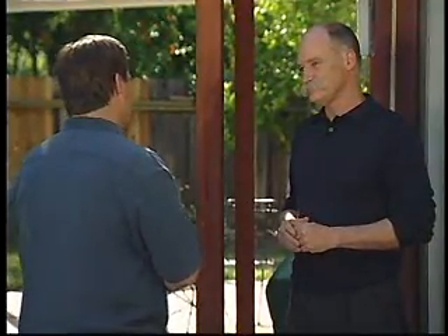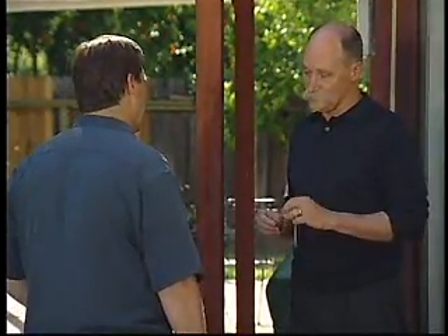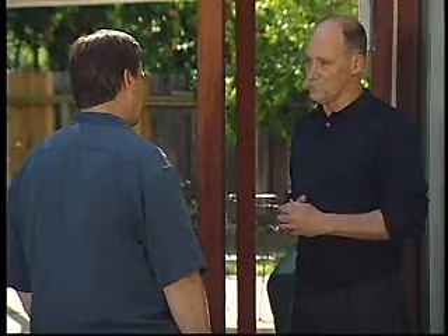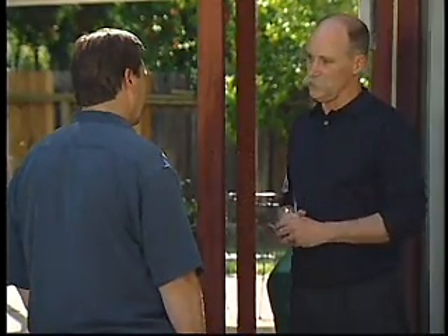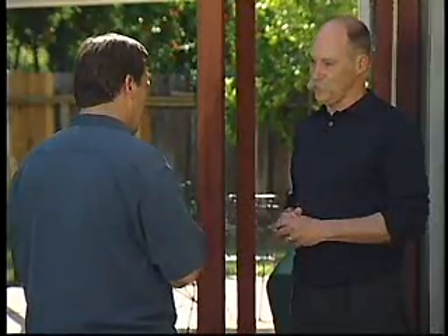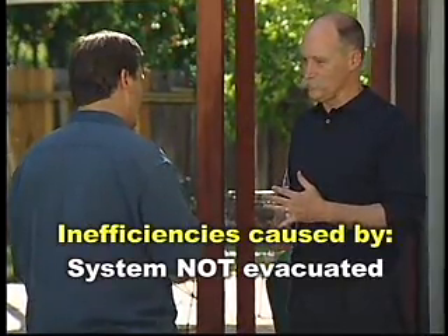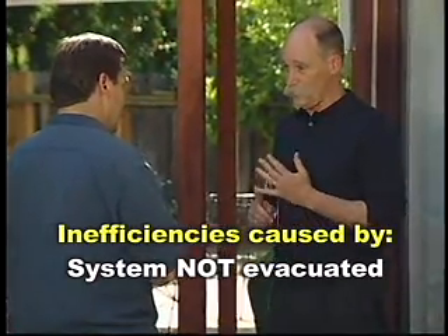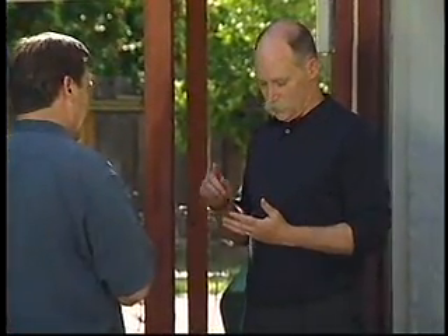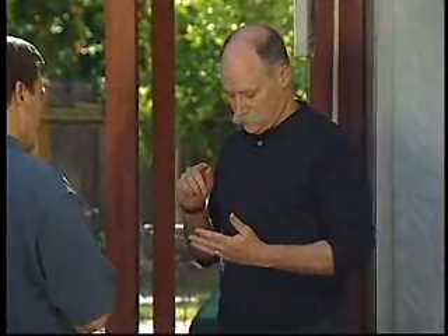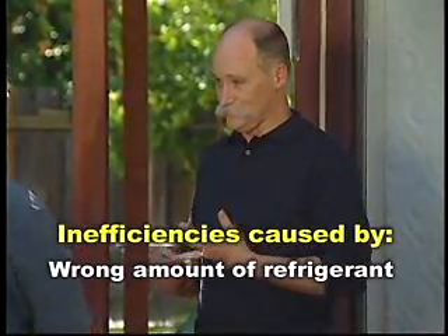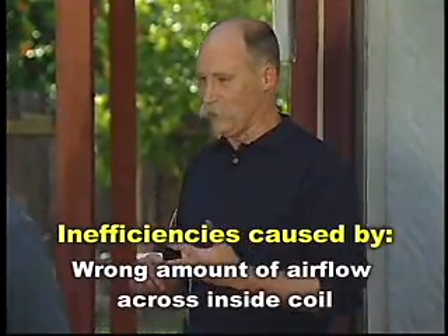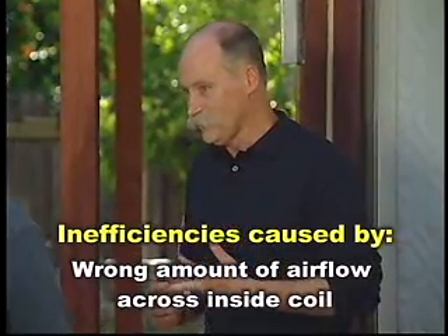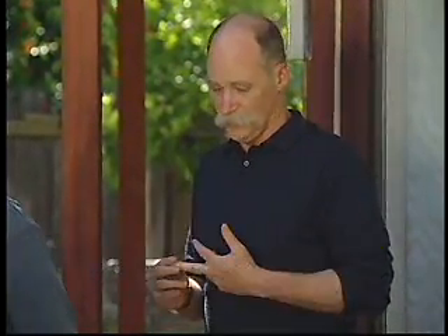What does that do to efficiency? Well, the efficiency drops way off because you have a good pressure drop going through there, and nothing's working right at that point. John, if we look at the hits that we take in efficiency on the installation of these units, what are they? Well, you're taking a hit when you don't evacuate the system, because what you end up with is air and moisture in the system. You're taking a hit when you don't have the right amount of refrigerant in the system, taking a hit when you have the wrong amount of airflow, when you have low airflow across the inside coil.